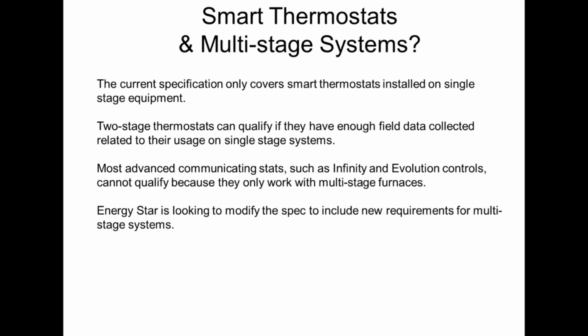The biggest issue for us is really communicating stats - stats that are smarter than smart stats. They don't have relays; they talk directly to the equipment, modulating gas valves and speeding up or slowing down compressor inverters. Those stats have a hard time qualifying because, like our Infinity and Evolution stats, they literally cannot be installed on a single stage furnace.